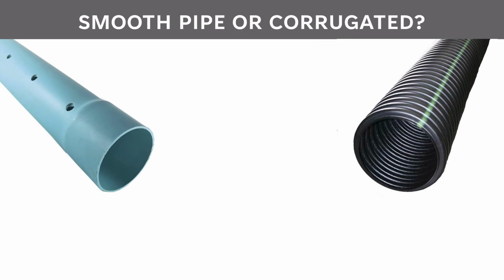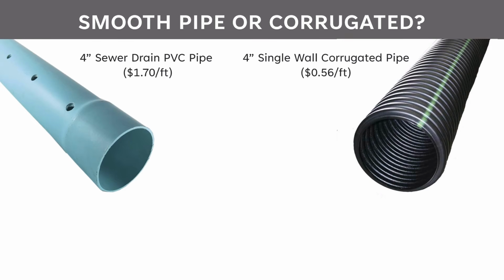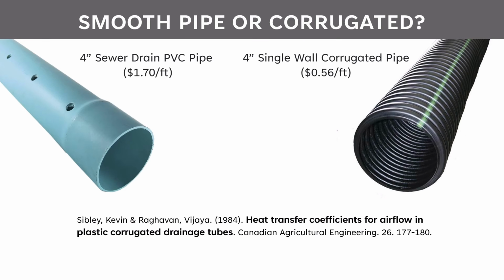Now that we know we are targeting 4-inch pipe, do we use a smooth or a corrugated pipe? Smooth pipe is $1.70 per foot, and corrugated pipe is 56 cents per foot. That's a 3x difference. Smooth wall pipe would have to be pretty dang good to make sense over a corrugated pipe. There are several papers out there that have characterized the heat transfer rate through these types of pipes. I'll highlight just this one from McGill University in Quebec.